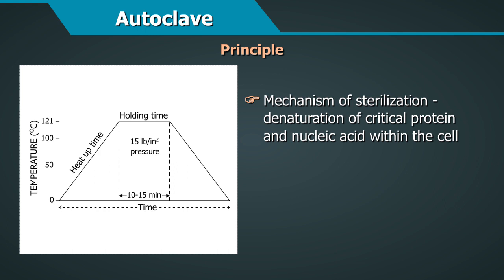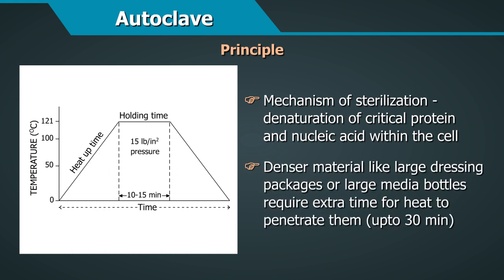The mechanism of sterilization involves denaturation of critical proteins and nucleic acids within the cell. Denser material, like large dressing packages or large media bottles, require extra time for the heat to penetrate, which may be up to 30 minutes.